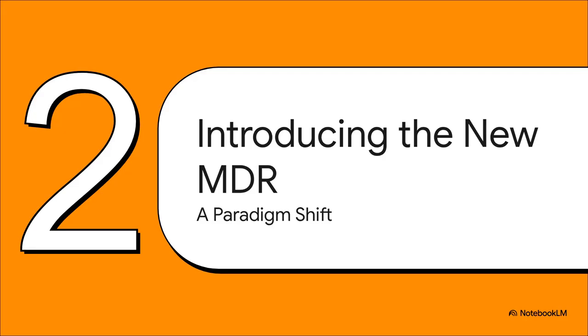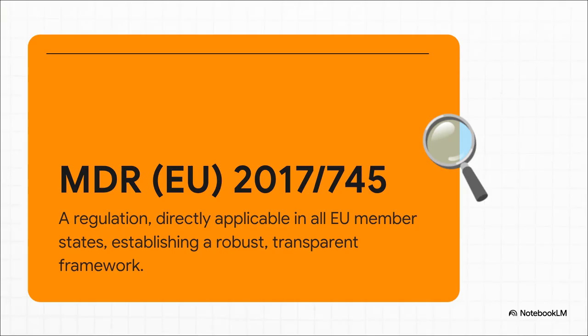Okay, so that brings us to the EU's big solution, the new Medical Device Regulation. And let me be clear, this wasn't just a minor update or a fresh coat of paint. It was a complete overhaul, a fundamental rethinking of the entire regulatory approach. And here it is, maybe the single most important change to understand. The MDR is a regulation, not a directive. What does that mean? It means it's a binding law that applies in its entirety directly across all EU member states. No more national interpretations, no more patchwork, just one single, harmonized set of rules for the entire market.